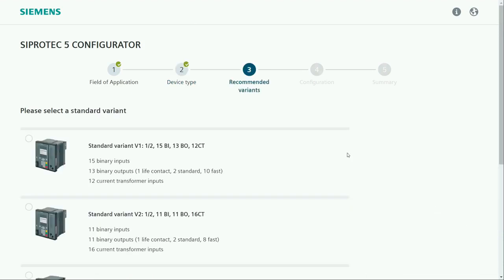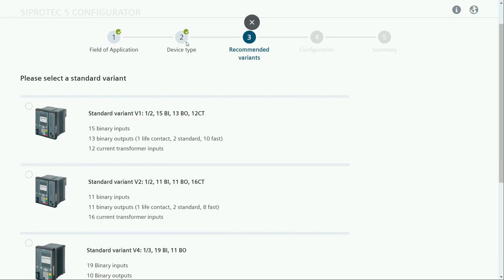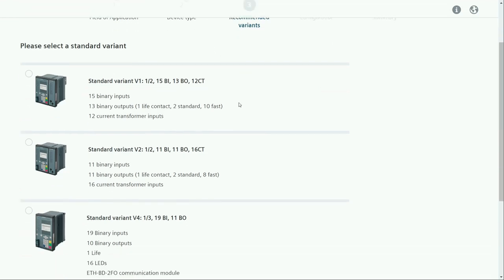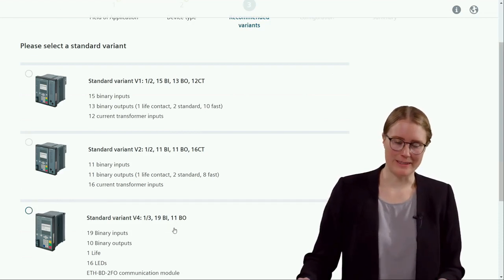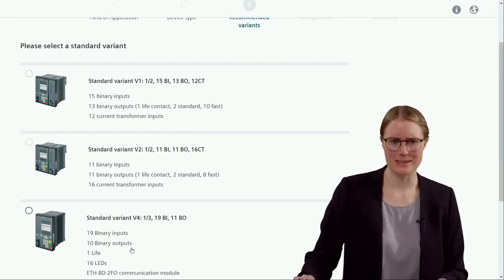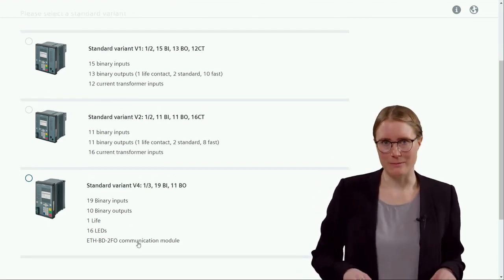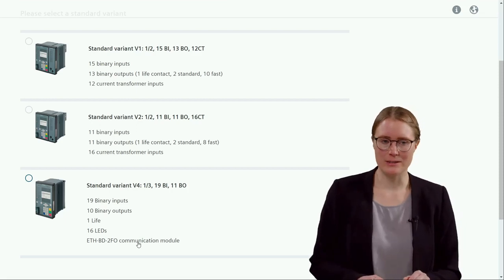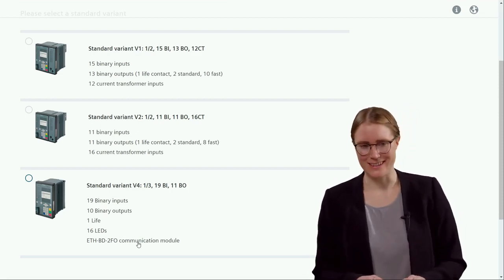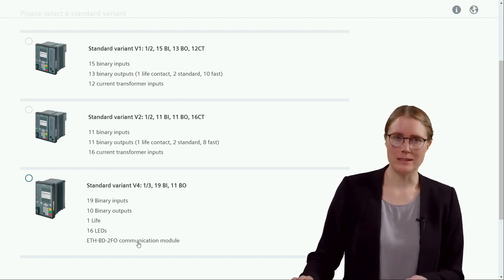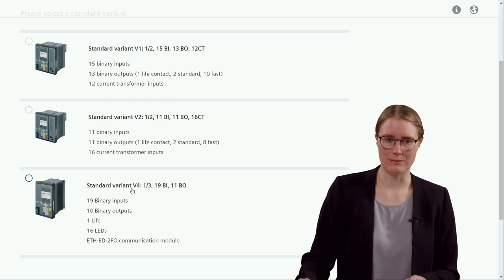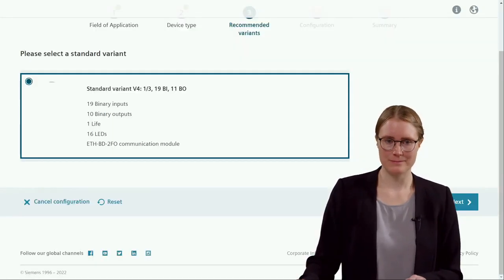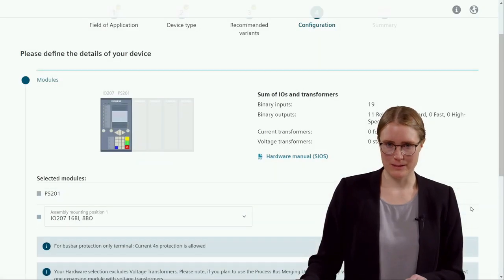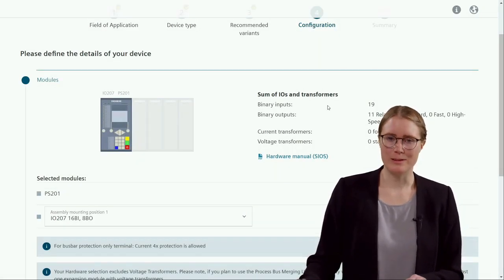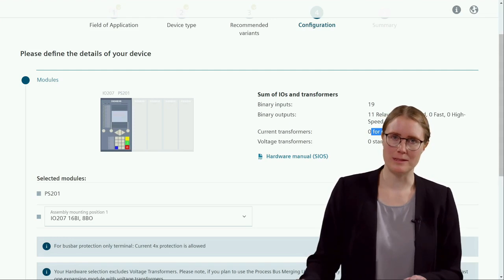Confirm the step. And as I explained a little bit before, here the standard variant V4 is interesting. This is always interesting for the fully distributed setup, because here all the process signals from the bays are connected to merging units, and the merging units are then connected to the 7SS85. So we don't need current inputs in the 7SS85 itself. I select this one and confirm this step. Once again, this overview of binary inputs and outputs, and as you see, 0 current transformer inputs in this case.